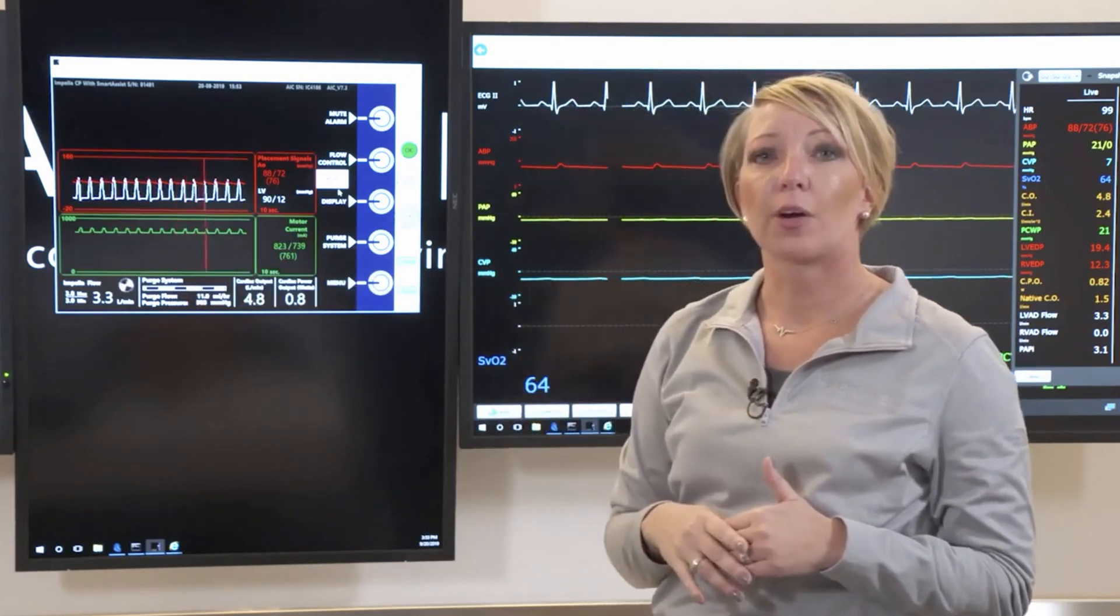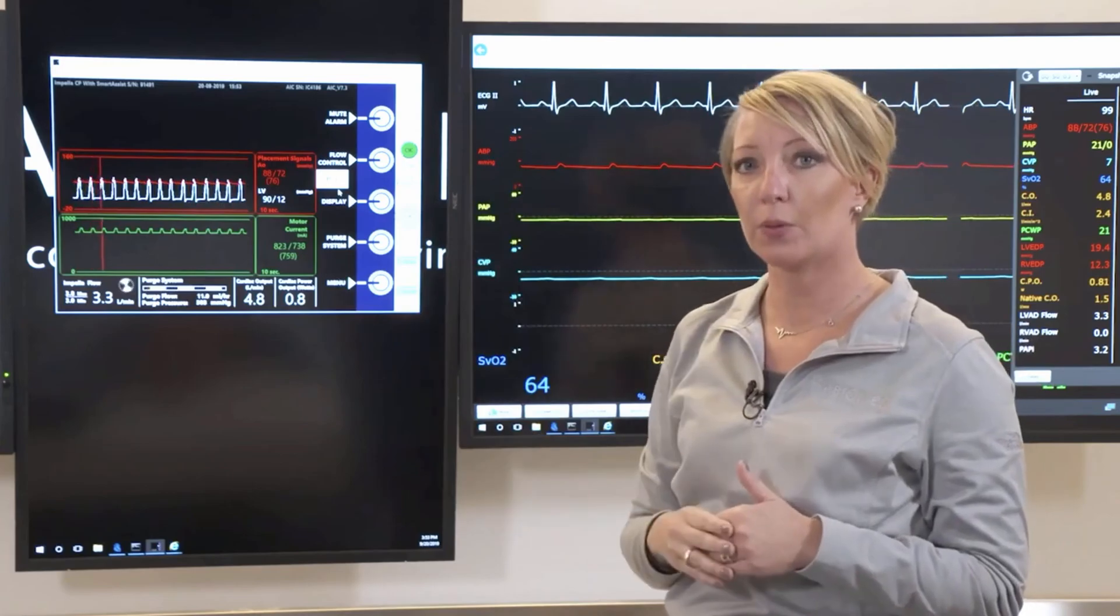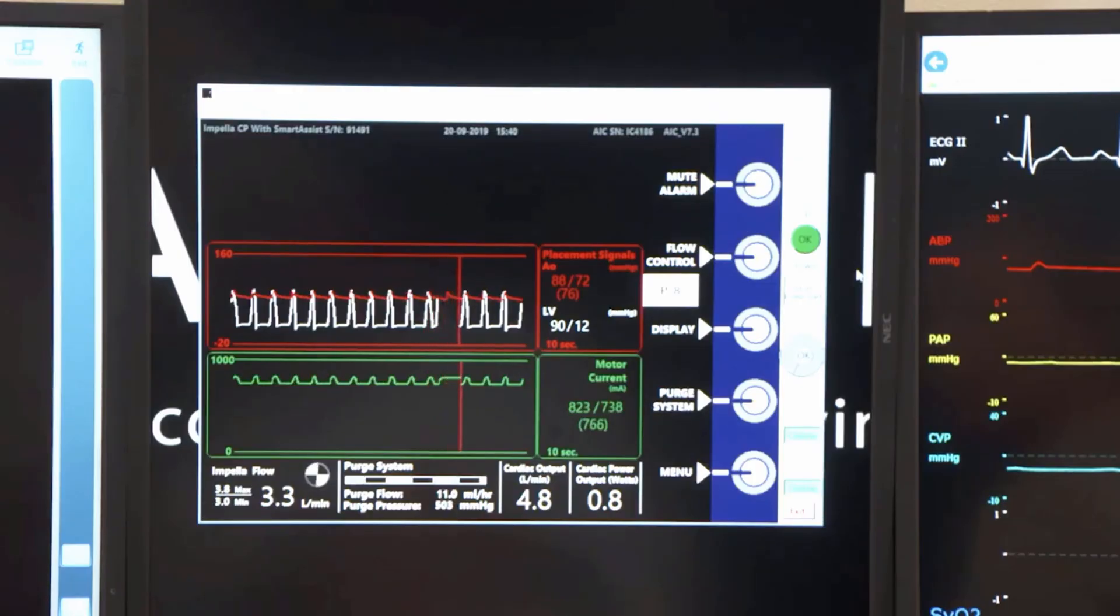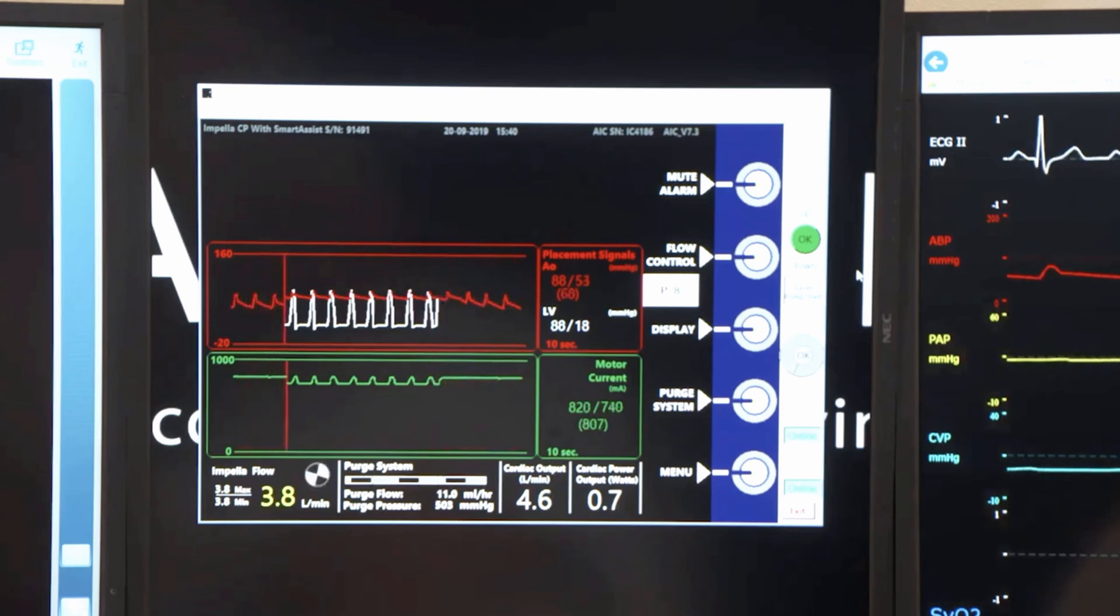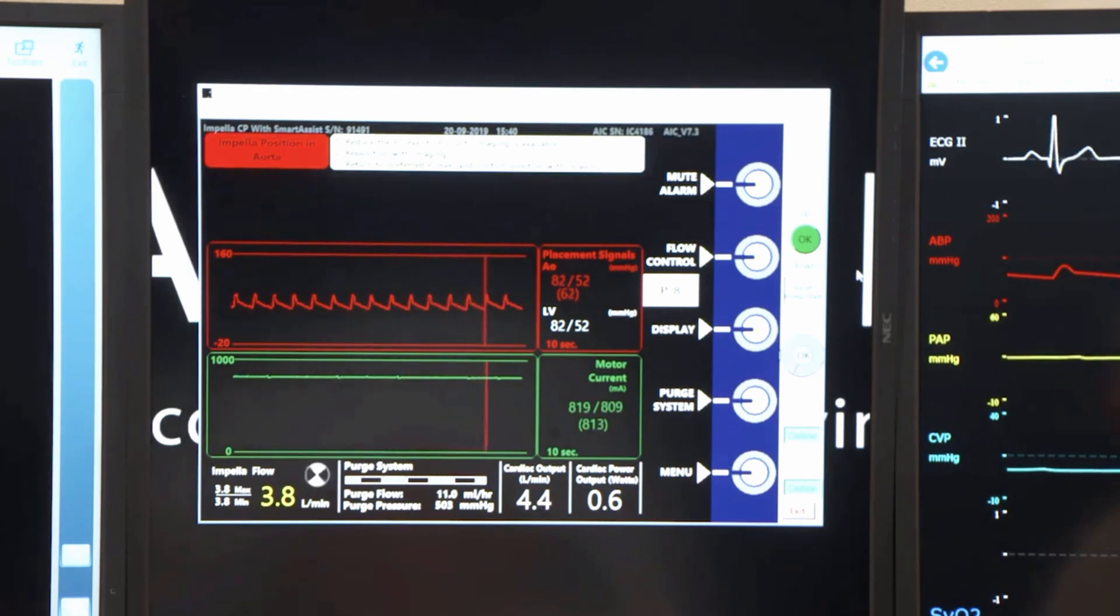When the device is in the correct position, we will have a nice pulsatile motor current. When the device is malpositioned or maybe drifts in or out, then it would be reflective of a flat motor current because the aortic valve is no longer creating that pressure gradient across the cannula.